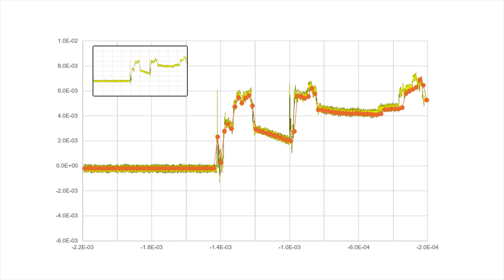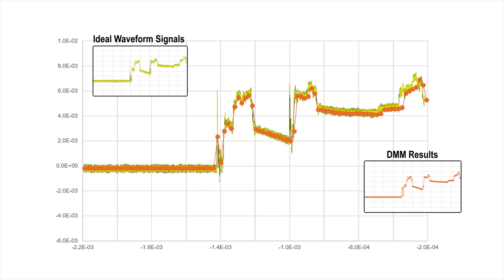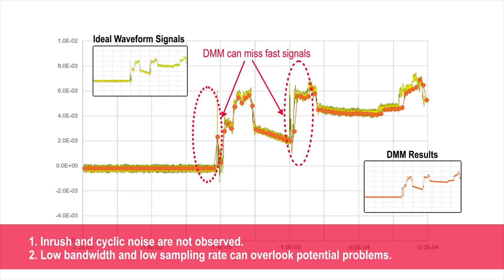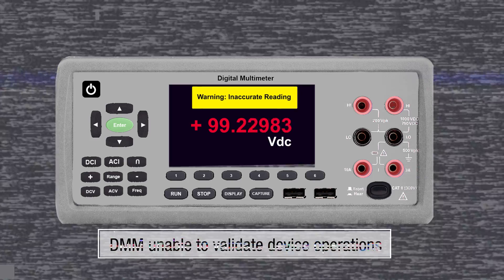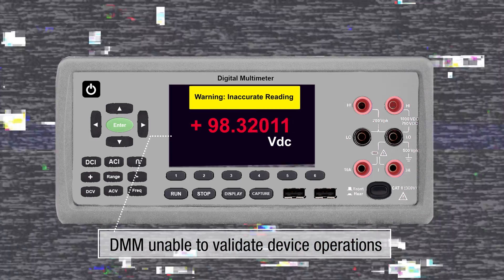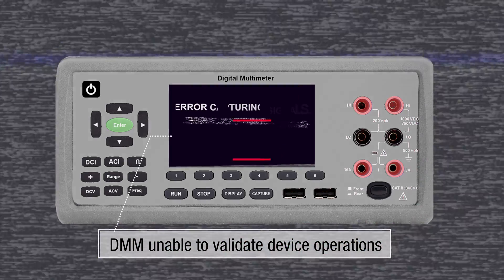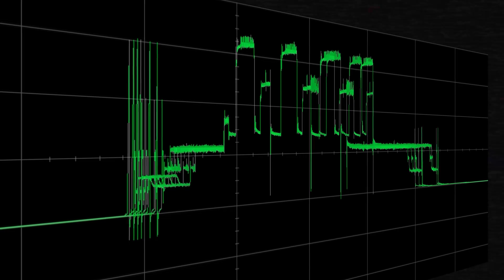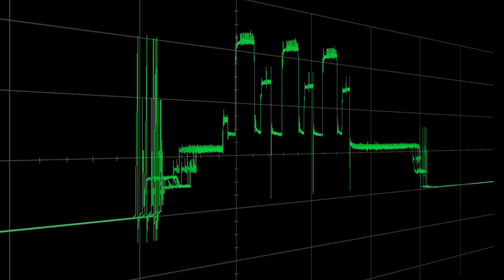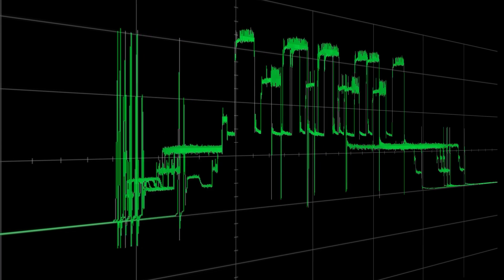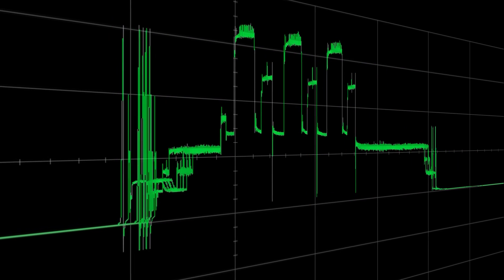While the DMM could measure the current values accurately, they found that the DMM's low bandwidth and low sampling rate could not capture the high transient signals like the inrush current or the device operations when it was active. The DMM could not validate the device operations precisely, especially at the high performance levels of the device. As many faults are transient in nature, the DMM could possibly overlook them too.